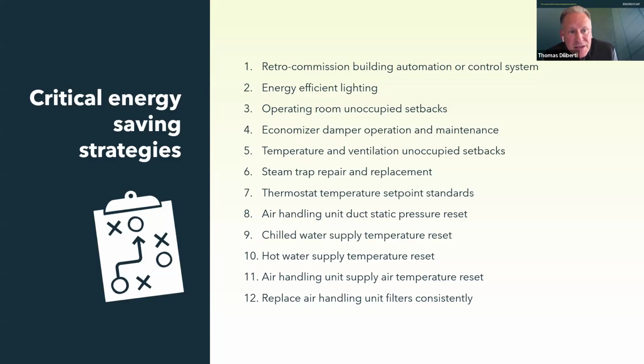But every other day of the year isn't the hottest day. The system should be able to recalibrate or reset itself to not make as much cold water, because it's not needed - that's the idea of a reset schedule. The system automatically adjusts because outside conditions and the building's needs have changed, and you have to accommodate those conditions. There are huge savings associated with that.